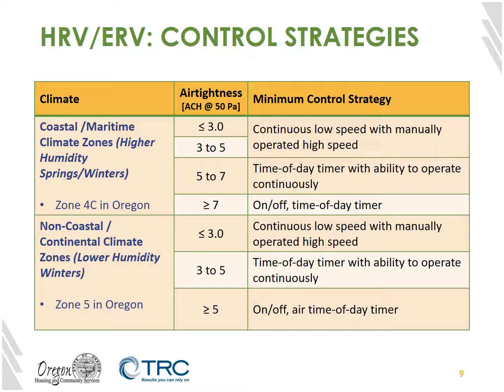When it comes to control strategies, the strategies themselves are actually pretty similar, whether we're talking about the coastal marine climate zones or the non-coastal climate zones, such as Eastern Oregon. Those are often referred to as climate zone 4C in Oregon for the marine climates, i.e. west of the mountains, and zone 5 in eastern Oregon or east of the mountains. The real difference is what building tightness level do you use a different control strategy.